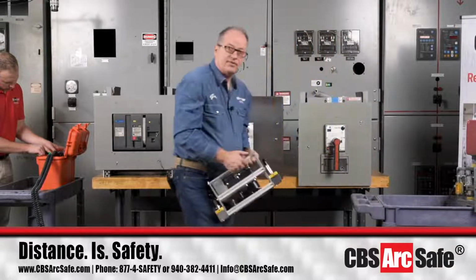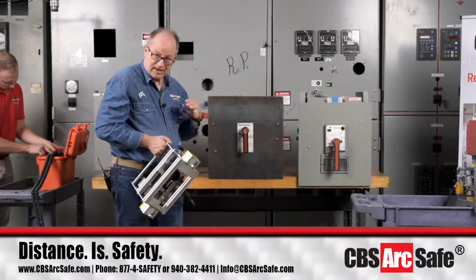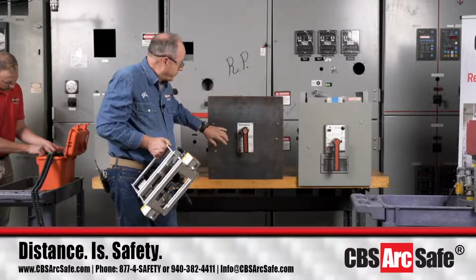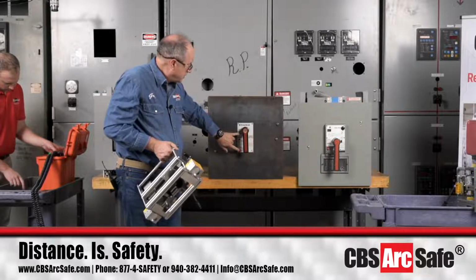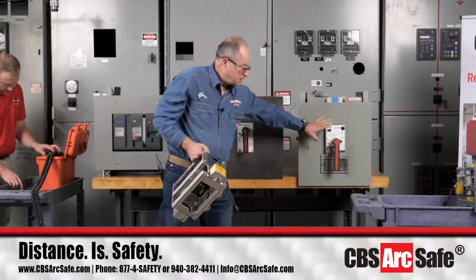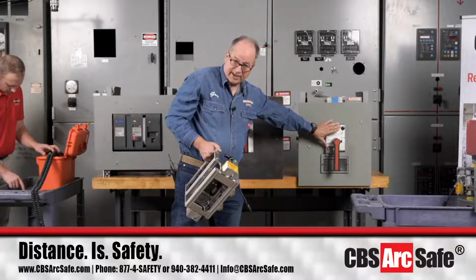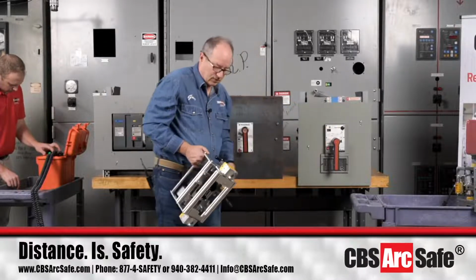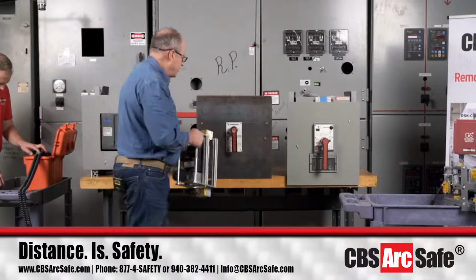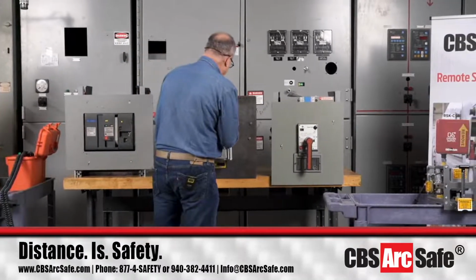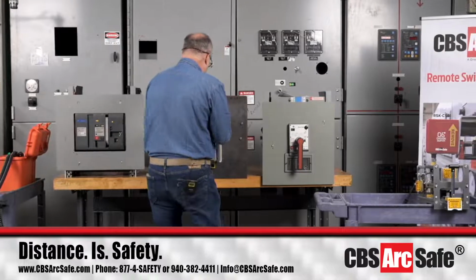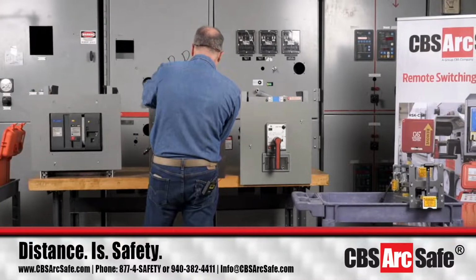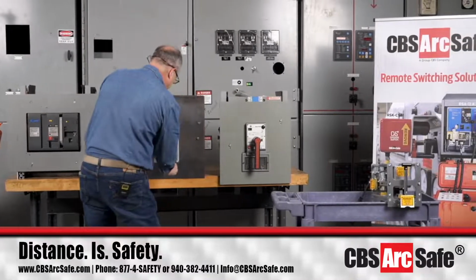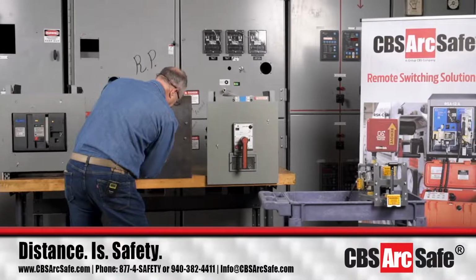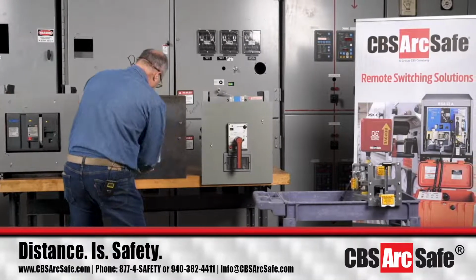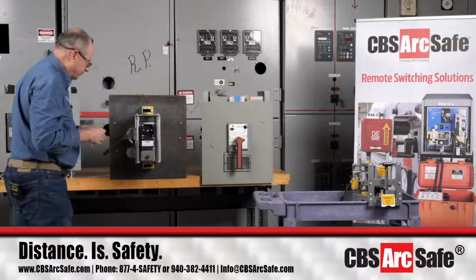Now, on the first generation, it's an RSA 91 series. If we compare this one, you can see I've got the close and trip buttons over here, and on this one they're on the diagonals. There's a lot of variation in the operating mechanisms, including electrically operated versions. You can tell those because you have a black button in the middle that you have to defeat to be able to manually operate the circuit breaker.